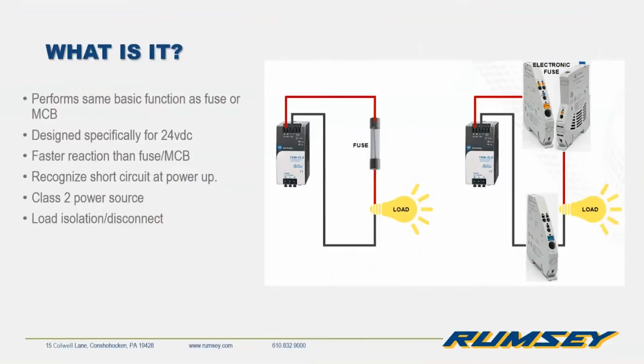So ECPs, or electronic circuit protectors, which we'll refer to as ECPs from here on out, are more sensitive. Electronic components are more sensitive than traditional electromechanical ones. Most fuses and mini circuit breakers were designed with AC in mind, and they can leave power supplies and other 24-volt components exposed, causing unexplained trips and damaged parts. So the 1694 takes a modular approach to solving these issues.